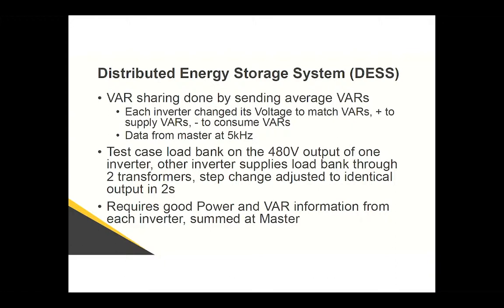So in order to see how well that worked, one of the things we did was we put a 480 volt load bank at the output of one of the 2 inverters. And so one inverter was feeding that load bank directly, and the other inverter fed through a transformer to the medium voltage system, back down through a transformer, and to that same load bank. And so with this system where we would send the average power in VARs, we were able to balance up that power in about 2 seconds. So that gave us nice information, but we needed to have good power and VAR and high-speed communication.